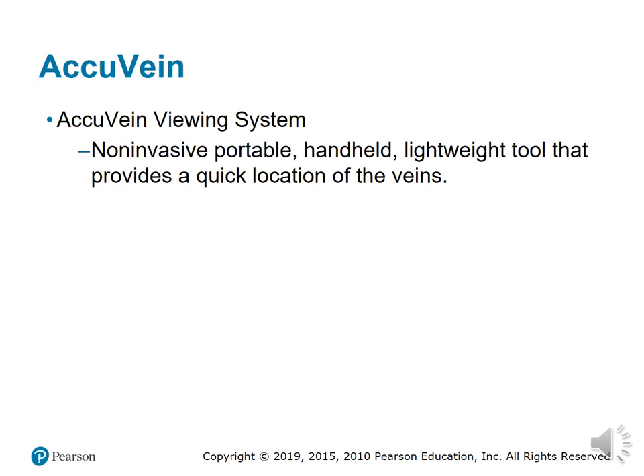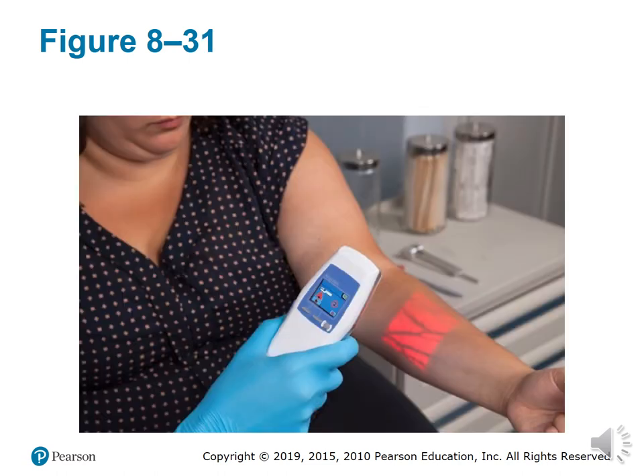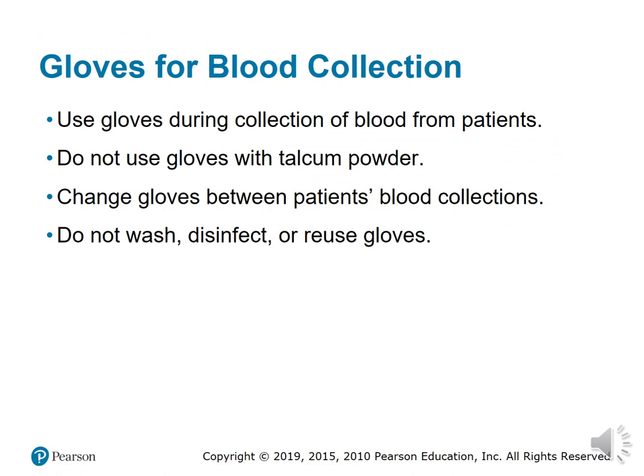The AccuVein is a non-invasive, portable, handheld, lightweight tool that improves patient outcomes for blood collection by quickly locating the vein. The AccuVein uses two lasers — one infrared and one red — that are rapidly scanned over the skin. The hemoglobin in the blood absorbs infrared light more than the surrounding tissue, and the device uses this change in reflection to determine where a vein is located.